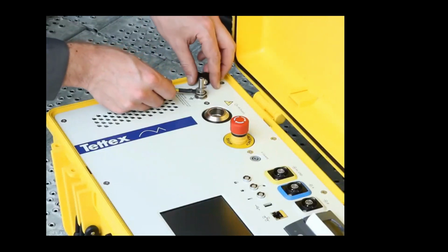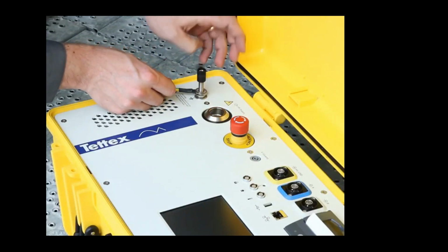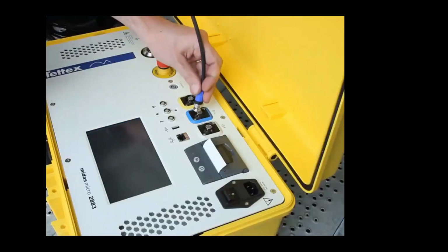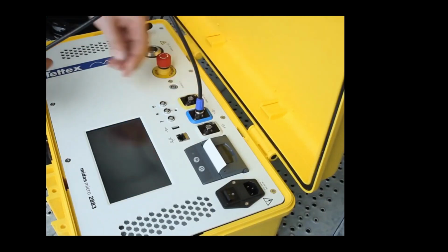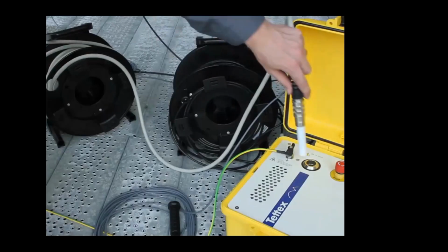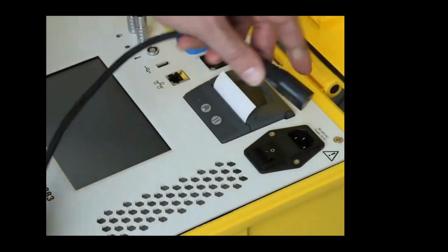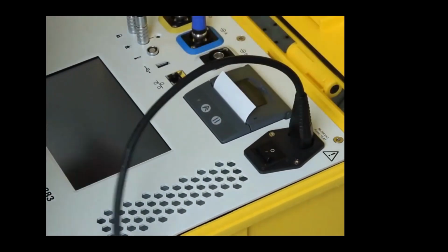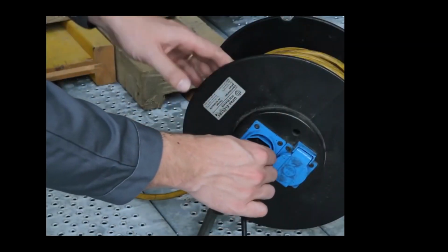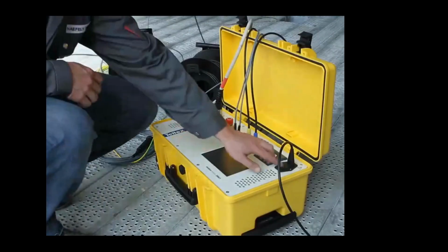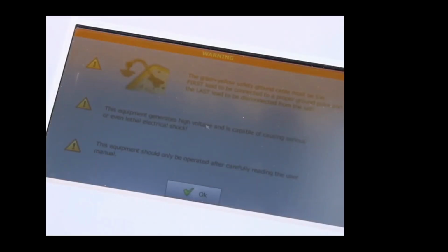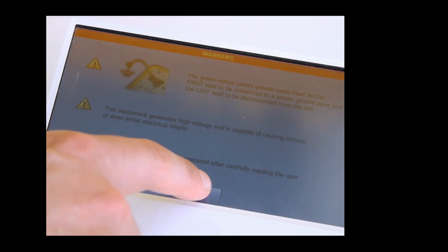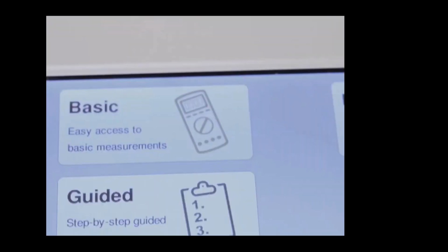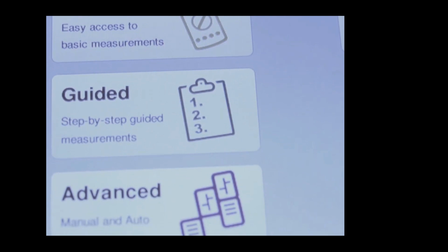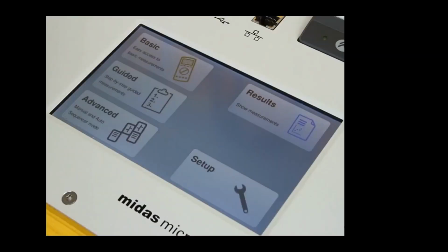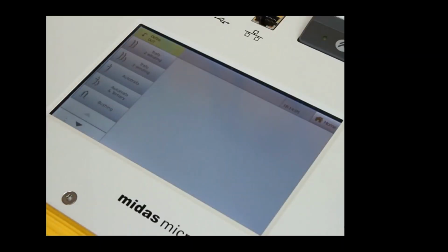To begin, first connect the green and yellow safety ground cable to the MIDAS Micro. After the unit is properly grounded, connect the remaining test leads and high voltage output cables. Finally, connect the mains power input connection. This should always be the last step in setting up the instrument. Once the unit is powered on, the user must read and confirm important safety information. The MIDAS Micro has 3 modes of operation: guide, basic, or advanced mode. For the purposes of this demonstration, we will select guide mode.